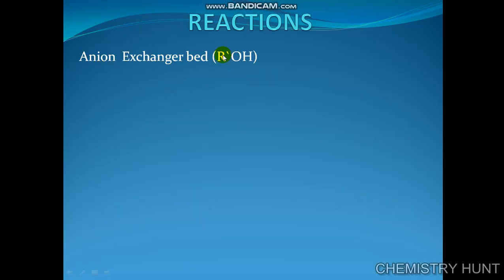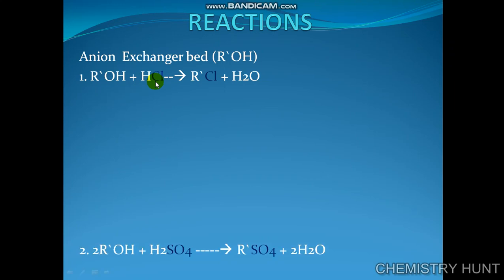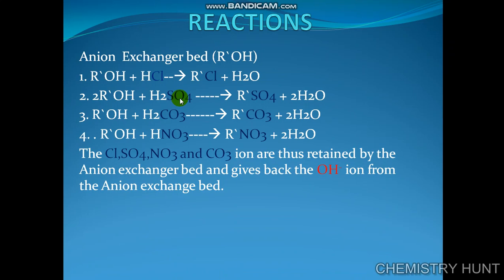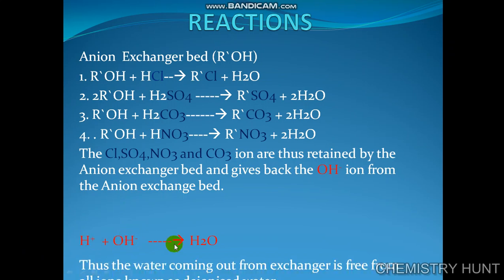For the anion exchanger bed reaction, represented by R'OH: the acidic water contains HCl, H₂SO₄, H₂CO₃, and HNO₃. All anions — chloride, sulfate, nitrate, and carbonate — are retained by the anion exchanger bed as R'Cl, R'SO₄, R'CO₃, and R'NO₃. The bed gives back hydroxide ions. From the cation exchanger we get hydrogen ions, from the anion exchanger we get hydroxide ions, and together we get deionized water.